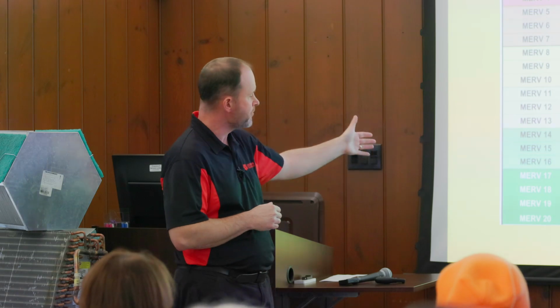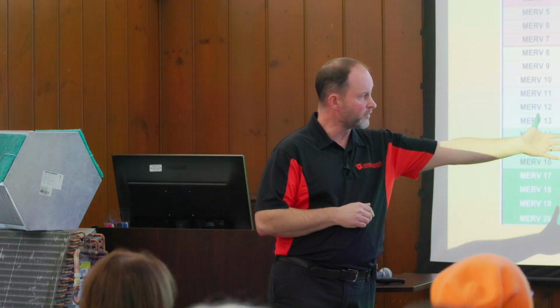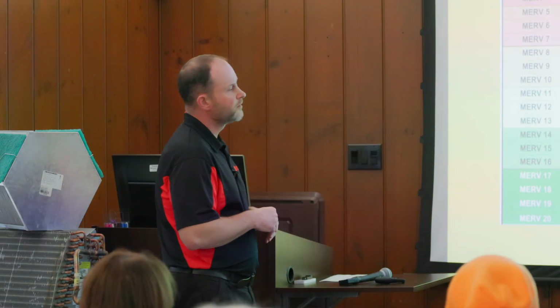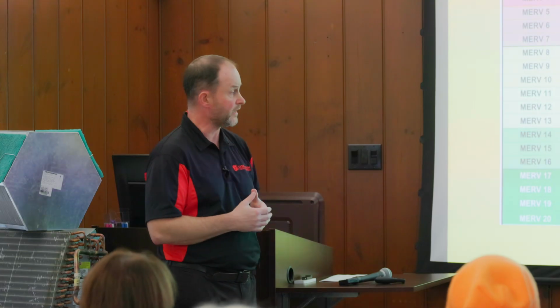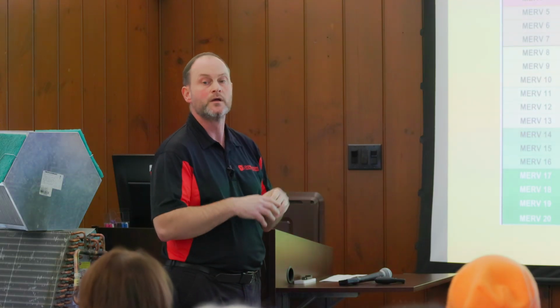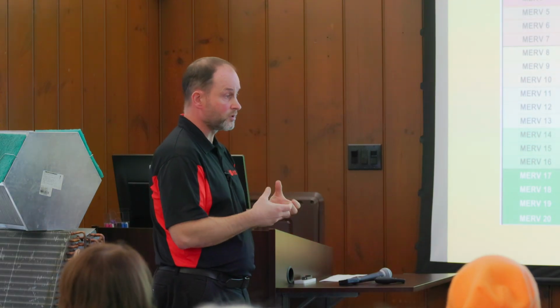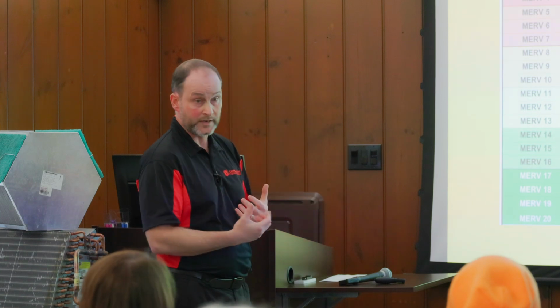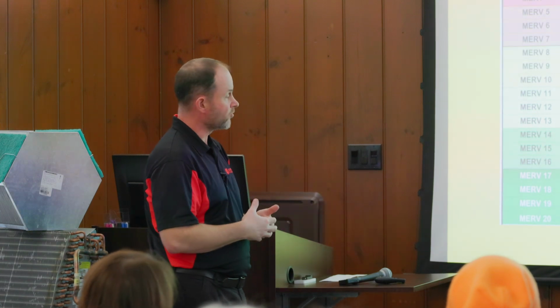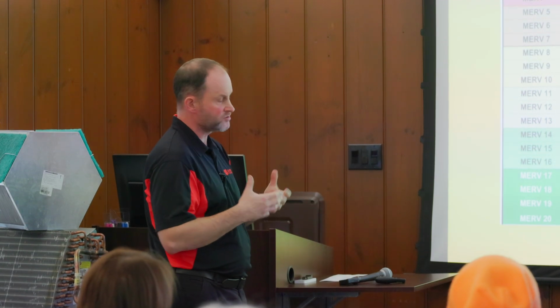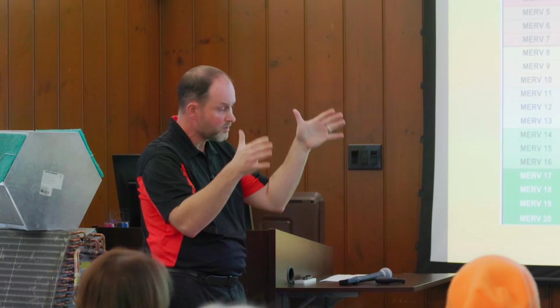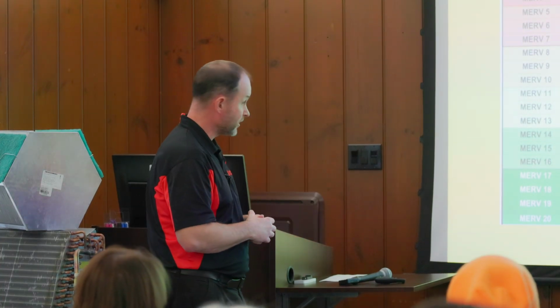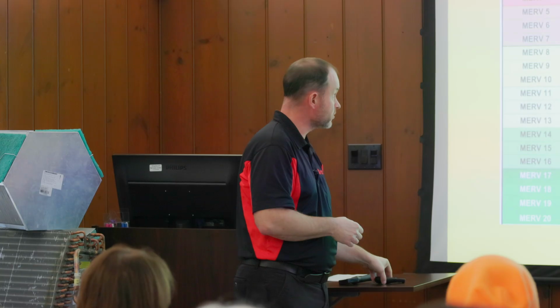You won't see it. But with MERV 20, you're probably all familiar with the word HEPA. That becomes HEPA filtration, and it comes in a bypass form. That will actually have its own motor, its own canister with its own piping connected to your ductwork to clean the air, because it's just too dense to have in the main ductwork. Your furnace fan motor won't be able to pull through and make it work.